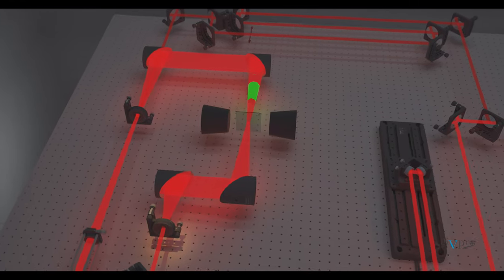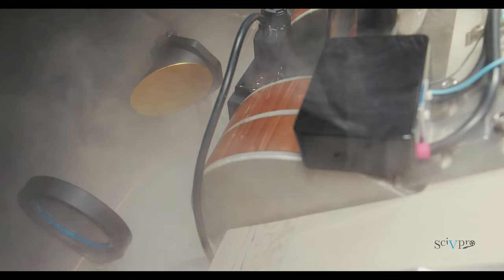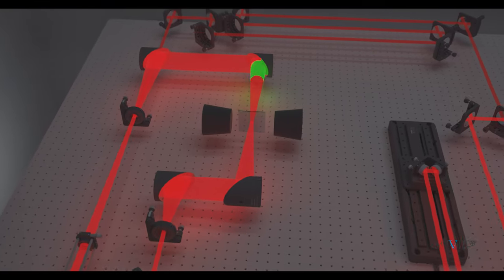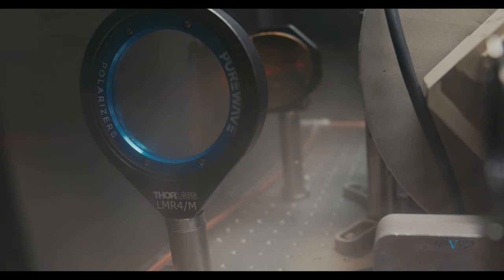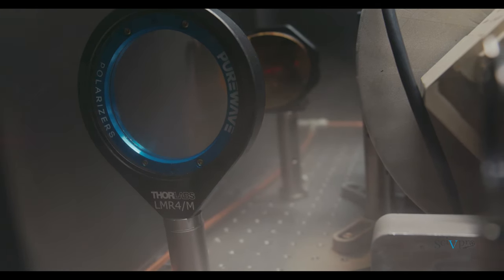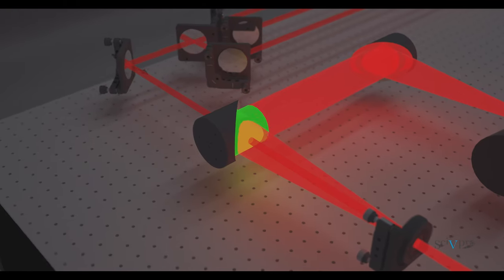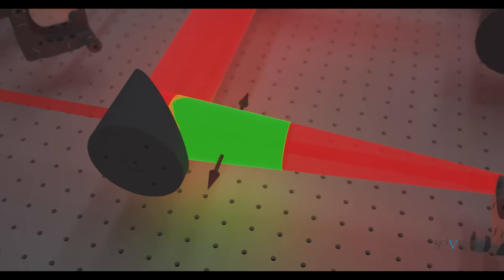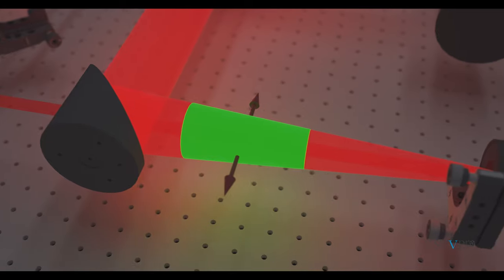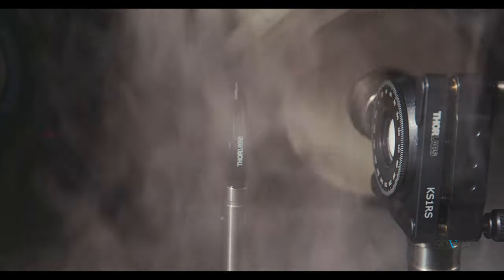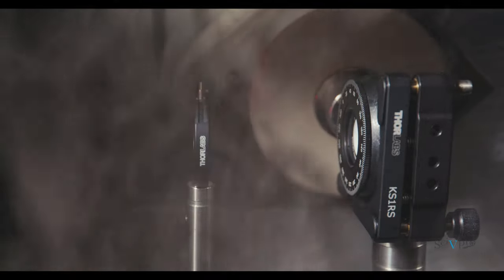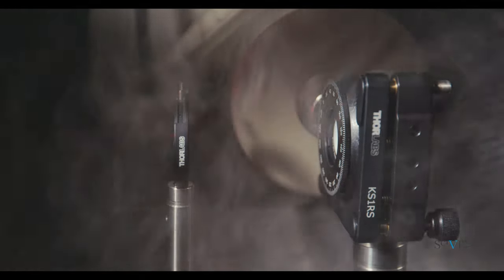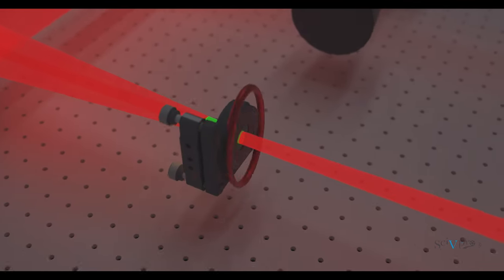The terahertz beam coming from the sample passes through a wire grid polarizer mounted on a motorized stage, goes through a parabolic mirror and through another wire grid polarizer before reaching a second parabolic mirror. The terahertz and probe beams meet at this parabolic mirror and travel together through the black box.